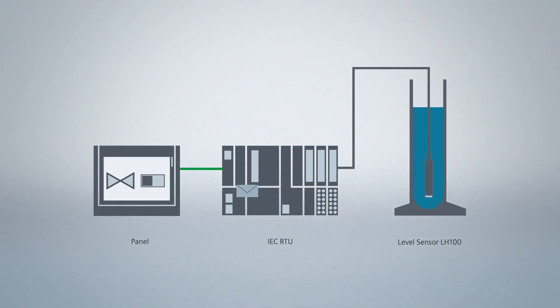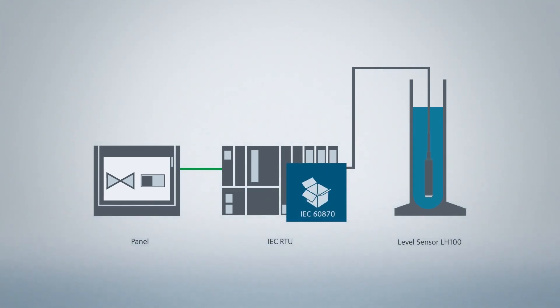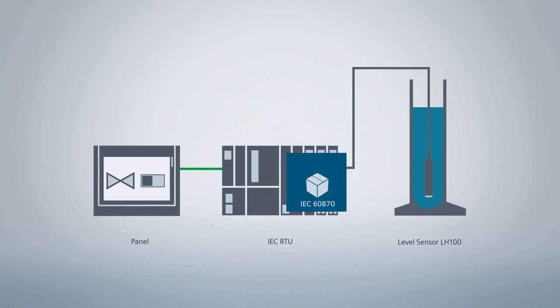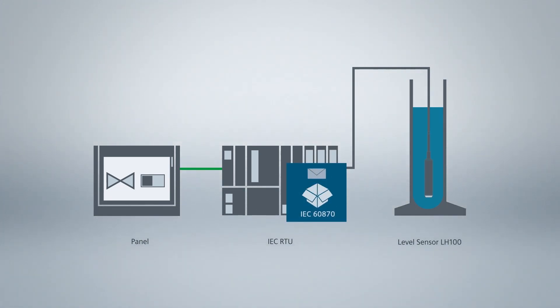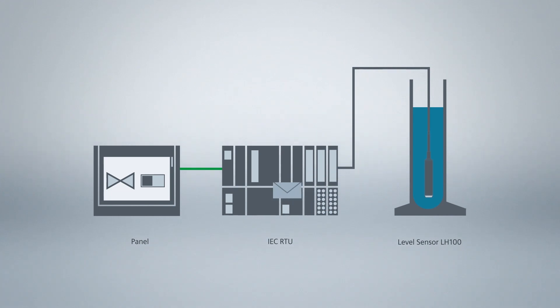The IEC control center is thus capable of establishing a connection to the RTU 20. However, no process data is transmitted yet. In order for our process data to be sent from the RTU 20 to the IEC master or commands to be received from the master, we create so-called data points in the data point editor of the CP. A data point is an IEC information object. It is read by the CP from the ET200SP CPU and transmitted as a process value via the IEC protocol. A data point can also be a command or set by the master to the RTU.